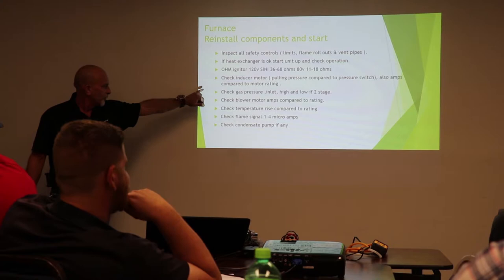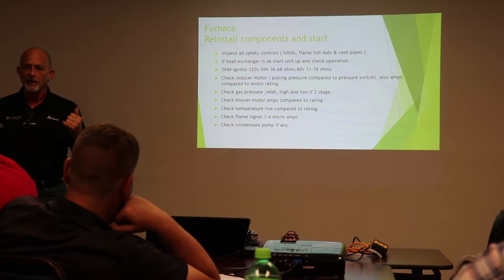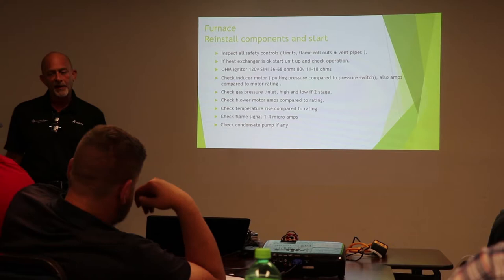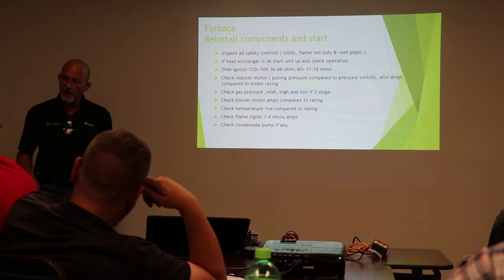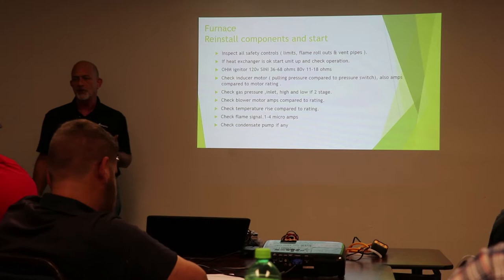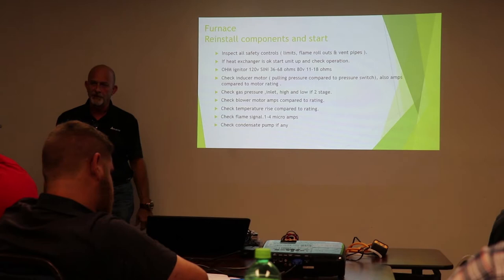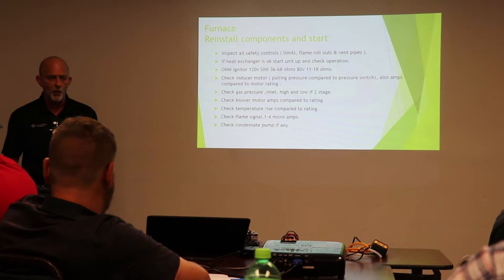So when we do our gas pressure, we also want to monitor our inlet at the same time. Inlet pressure, we always set to have a minimum. Manufacturers say 4.5. I prefer 5 for one reason. 3.5-inch manifold pressure on a normal natural gas furnace. Every gas valve made has a 1-inch differential built into it. If we're at 3.5 out and we get to 4.5 in, what happens, guys? Pressure switch will close. Gas valve closes. We don't have that 1-inch differential.